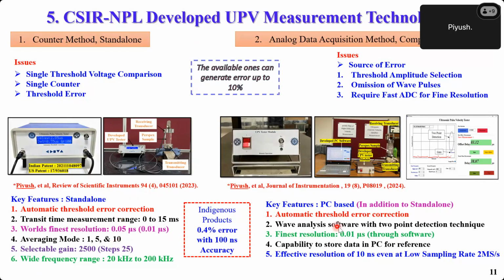And these are the key features of both instruments. Like, the counter method has automatic threshold error correction, which I will explain in later slides. It has a transit time measurement range from 0 to 15 millisecond, which is not available in the previous one. It has the world's finest resolution, which is 50 nanosecond, and in the averaging mode, it is 10 nanosecond. It has three averaging modes, 1, 5, and 10, and we can select multiple gain in steps of 25, up to 2500. So we can go up to 2 meter or 3 meter with the help of this instrument.